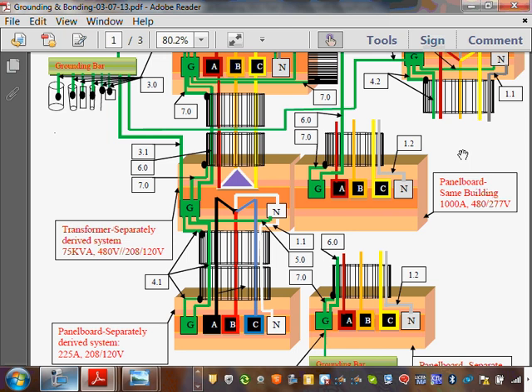How would you make a connection? Take that neutral here and tie it to this neutral here. Now that's a non-separately derived system. Not that you would do that. You wouldn't do that on the 208, 120, 277. These are two different neutrals. My white neutral is 120. My neutral up there is a 277 neutral. Okay, so that's what they call a separately derived system.